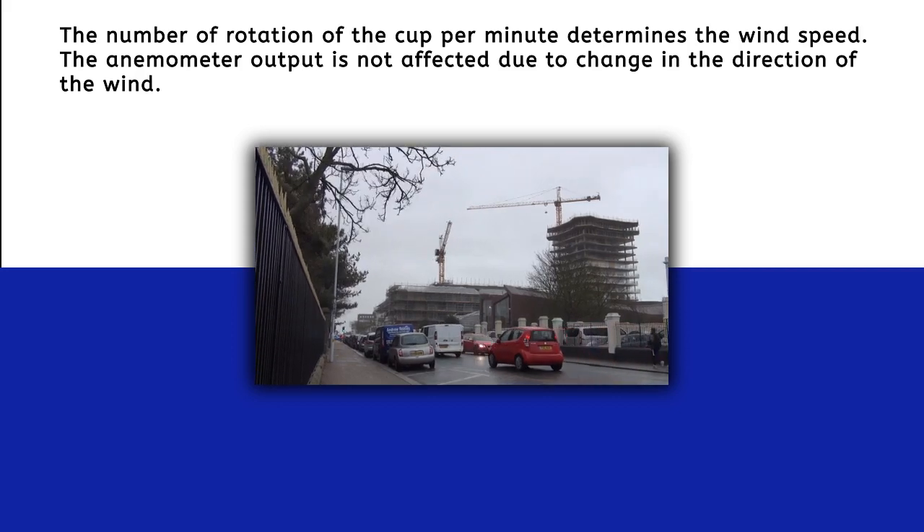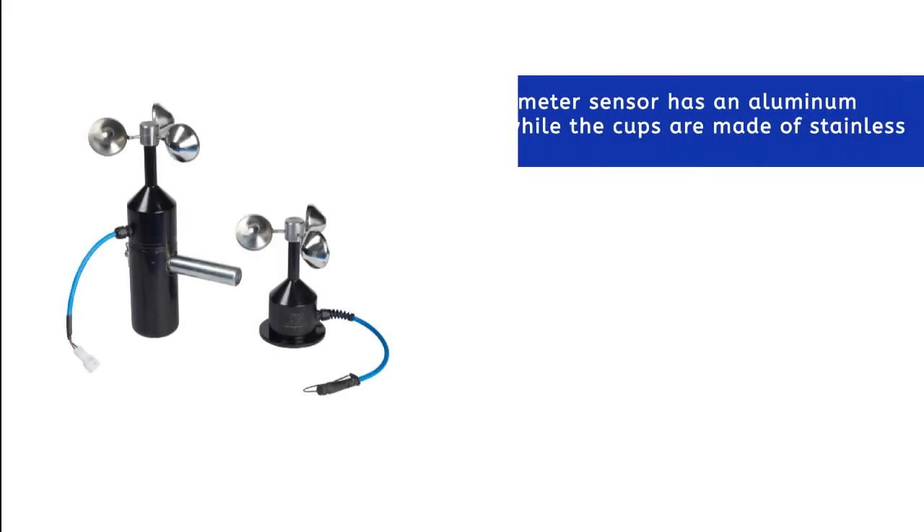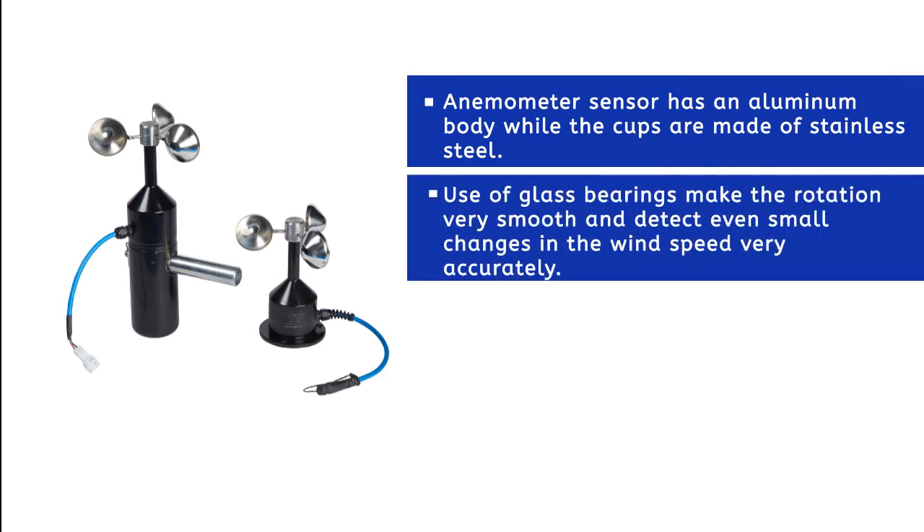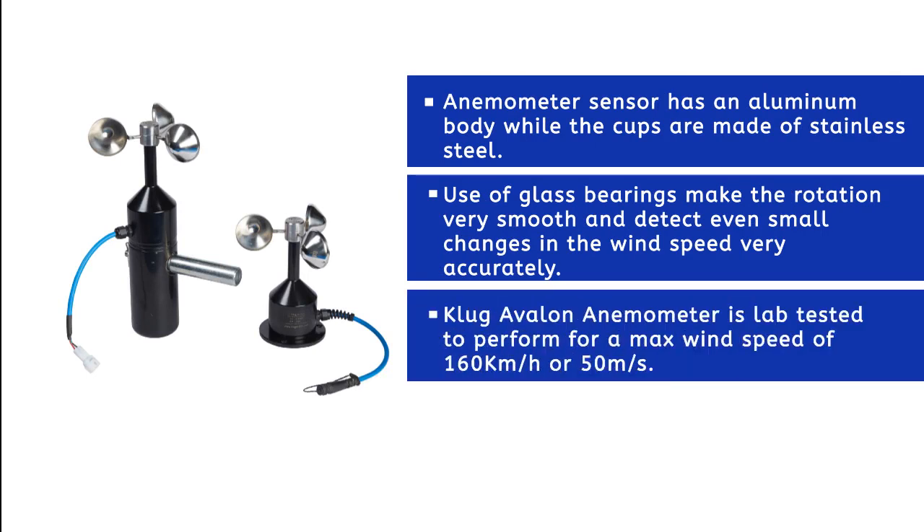The anemometer sensor has an aluminium body while the cups are made of stainless steel. The use of glass bearings makes the rotation very smooth and detects even small changes in wind speed accurately. The Klug Avalon anemometer is lab tested to perform at a maximum wind speed of 160 kilometers per hour, or 50 meters per second.